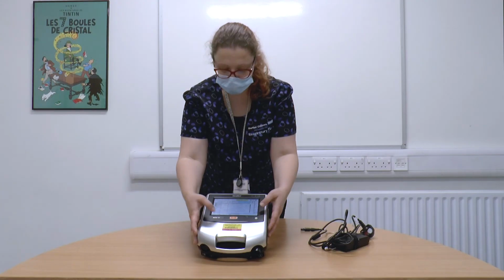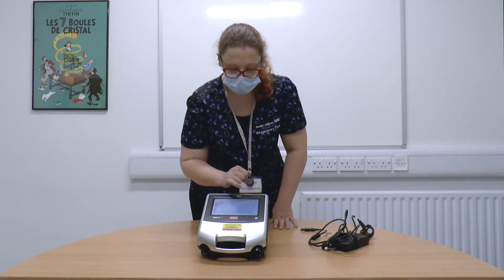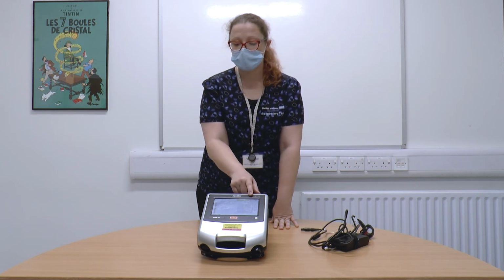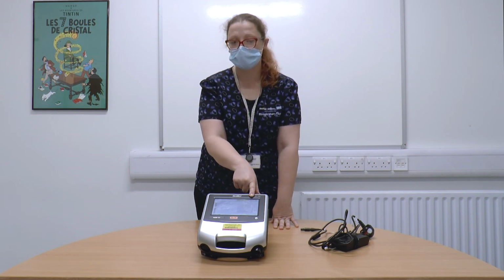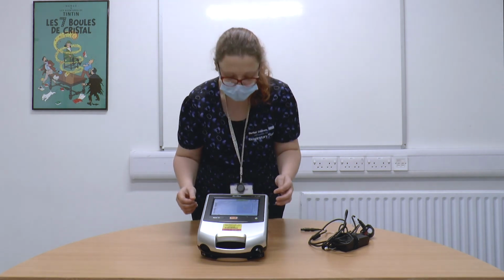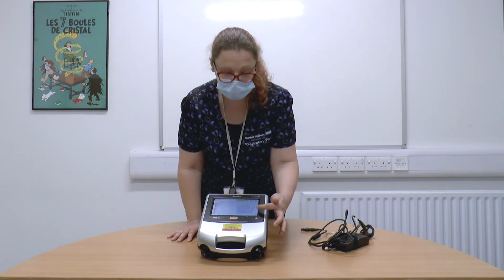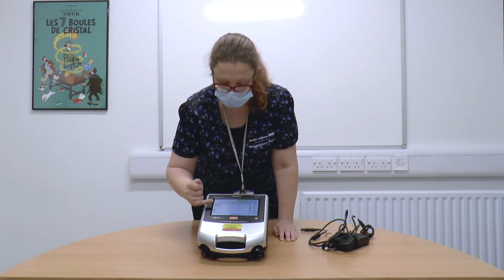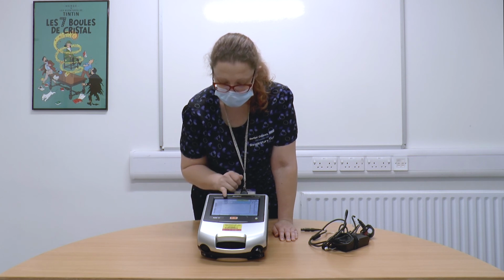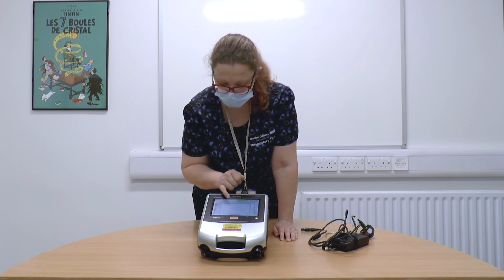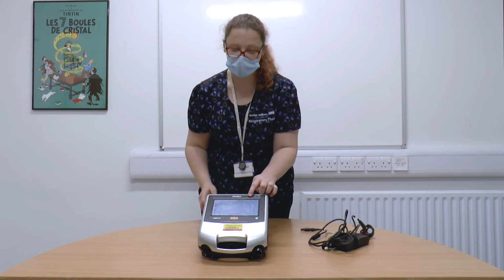On the ventilator screen, no matter where you are, there is always a picture of a battery at the top of the screen. It will tell you the percentage of battery you have left. If there is just the internal battery, rely on having 4 hours if it's fully charged. You may have an external battery plugged into where the power socket goes at the rear. If that is fully charged, you will have another 4 hours. If you want full battery information, if you press the I, press battery, it will tell you exactly how much charge is left, and it will tell you if any maintenance is required. Most families will just rely on the percentage. If in doubt, always take your charge cable with you.